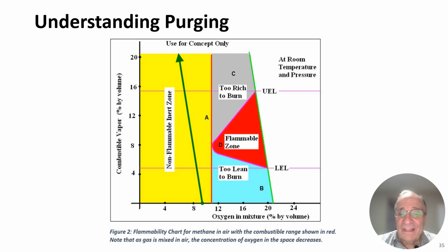Well, then your whole flammable zone is totally different than what's shown here, because now you're already at conditions that are very near the ignition point of natural gas temperature. So that insulation barrier does a lot less to prevent flame propagation from occurring. So this profile that I'm showing you here is really intended for atmospheric conditions.